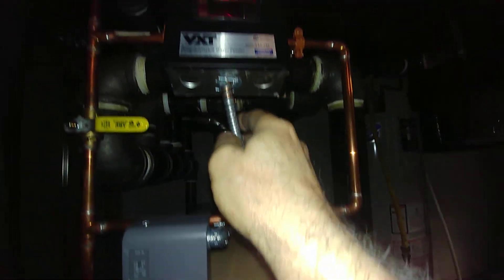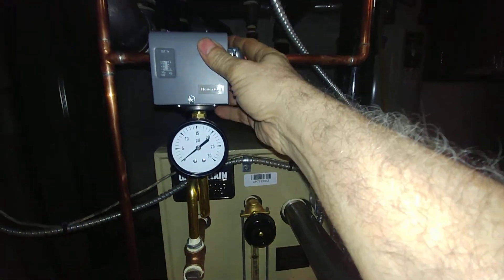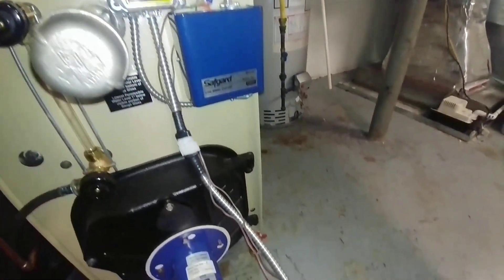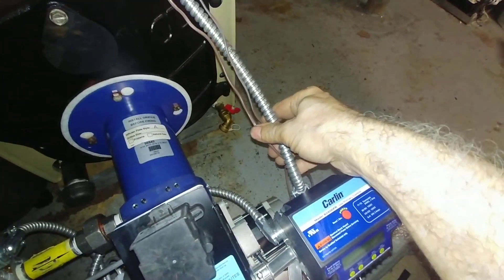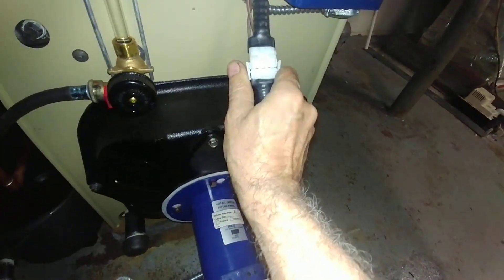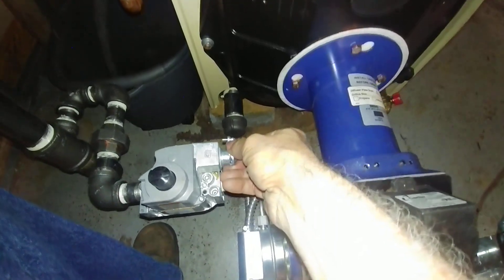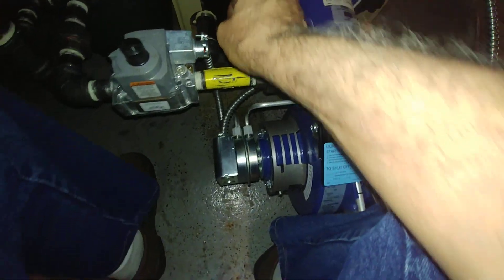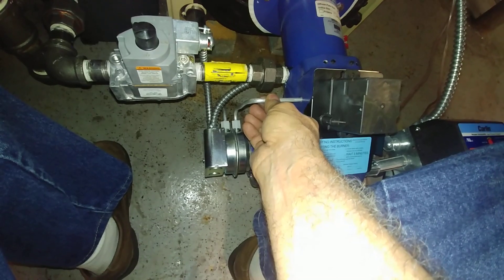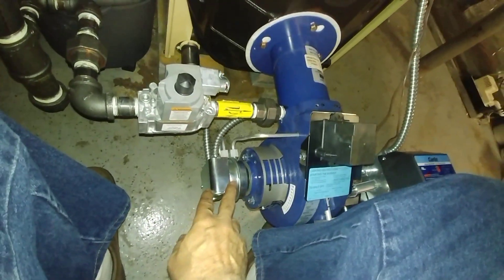From there, power is sent to the lower cutoff and also to the VXT, and a line is sent to the Pressuretrol. Finally, power is sent to the fire control box on the burner. We have a quick disconnect here so we can open up the box without disassembling any wires. The 120 volt power is here — this is the blower circuit — making sure that the motor is working and indeed inducing a draft at this point.